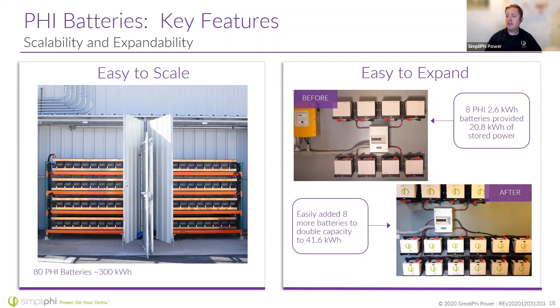The picture on the right is what it looked like to come back to a home. They had 8 batteries, we were able to add 8 more batteries. We used that existing combiner box, and that SMA Sunny Island there is still existing. Really, all we had to do is change a little of the set points, and you're off to the races.